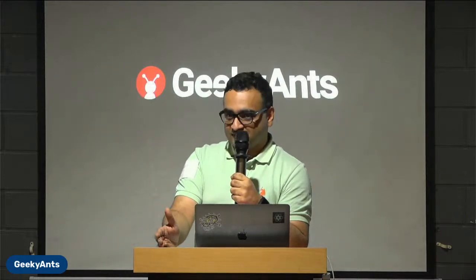It takes 6 to 9 months for the FDA to come back to you. They will come back and say, okay, this is good to go or not good to go. So it's a long drawn out process. I've been through it, and a couple of other speakers have been through it, so it's a lengthy process.